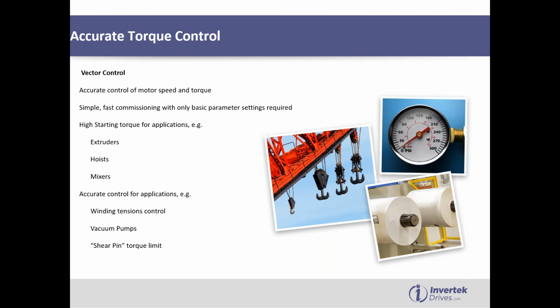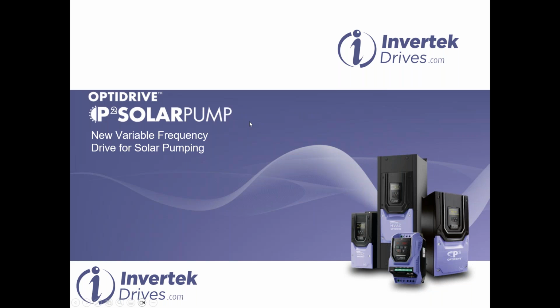In other applications, so winding tension, vacuum pumps, we have very good torque control mode there where we tell the drive you need to stay at this level of torque on this, or you need to keep this level of torque on this motor. But we also have a shear pin torque limit. So instead of using a mechanical shear pin in a gearbox, we can do a shear pin torque limit in the drive electronically. So again, that's a brief overview of the P2 drive and the main applications.